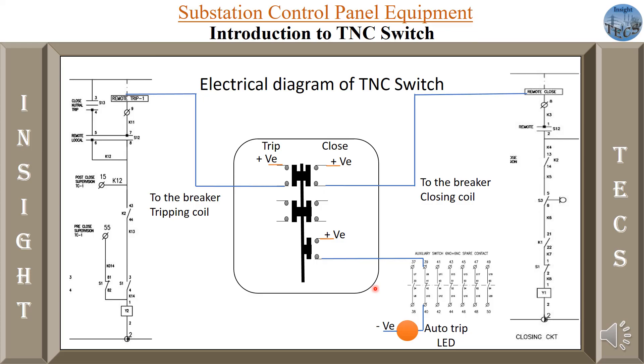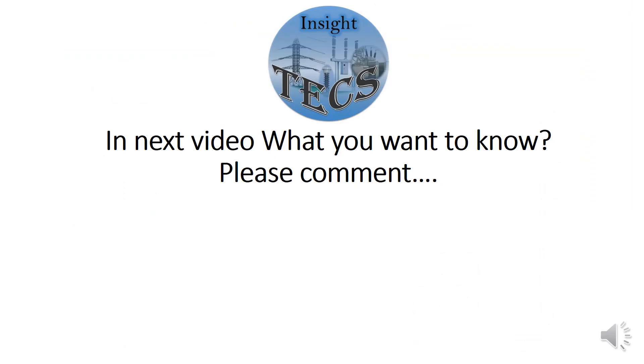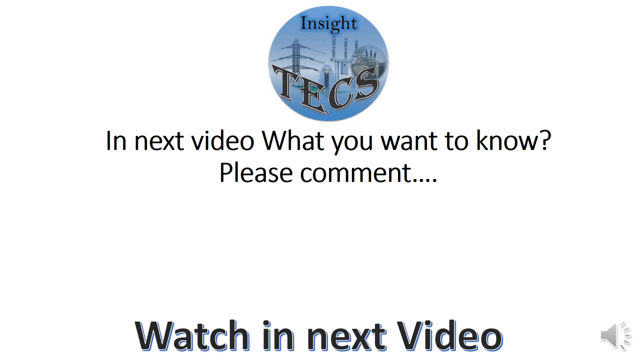In the normal situation, whenever you close the TNC switch, the circuit breaker actually closes, so the auxiliary switch becomes NO. The positive supply does not reach the LED, and the auto trip LED will not glow on the panel. So, auto trip is a basic indication of any malfunction — if the breaker is not actually closed. That is the importance of auto trip and the TNC switch in the control panel. I hope you have understood these basic concepts. Please let us know what you want to learn in the comments section. Thank you.